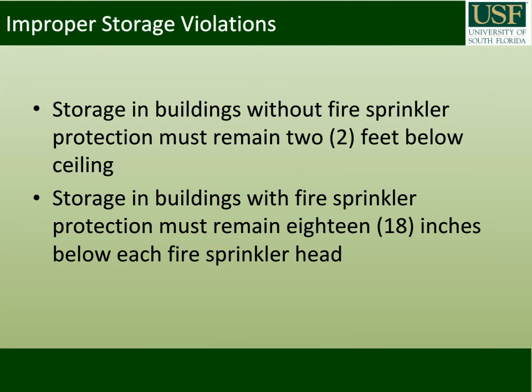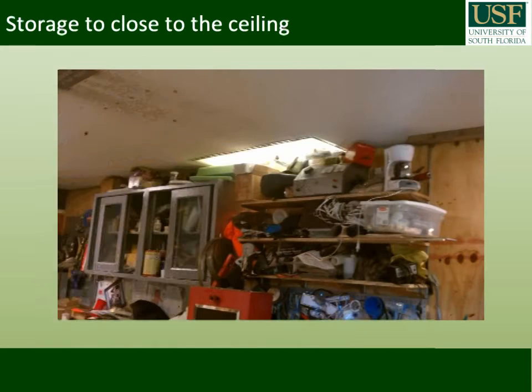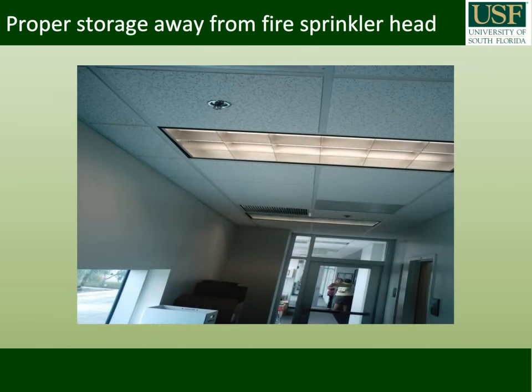Storage. Storage in buildings that do not have fire sprinkler protection must remain 2 feet below the building's ceiling. Buildings that have a fire sprinkler system must keep their storage 18 inches below each fire sprinkler head. Shown is an example of storage that is too close to the ceiling. Here is an example of storage clear of the fire sprinkler head.